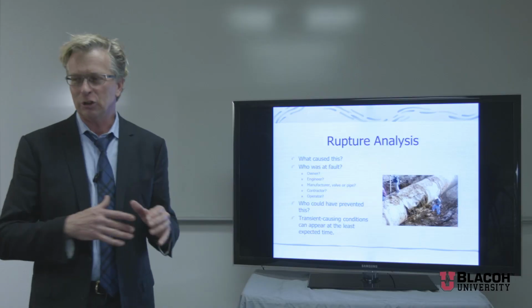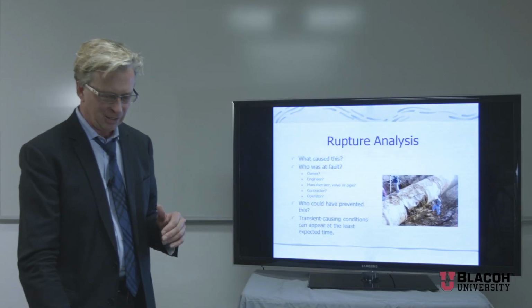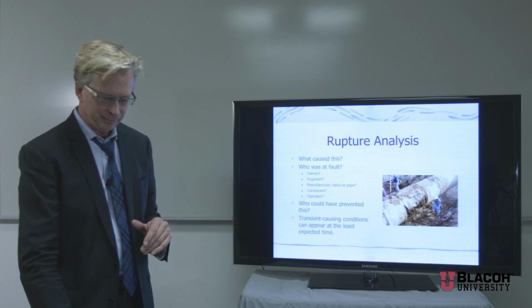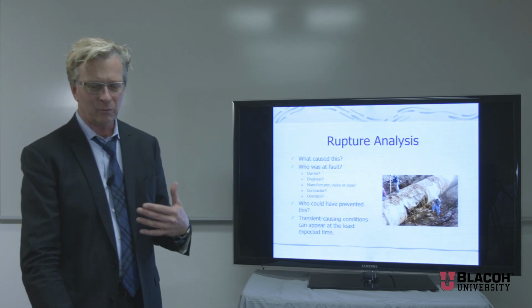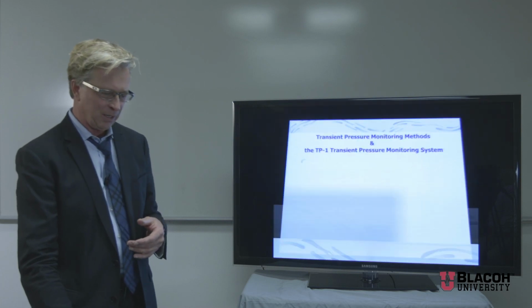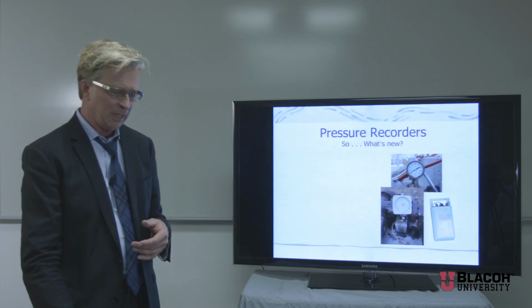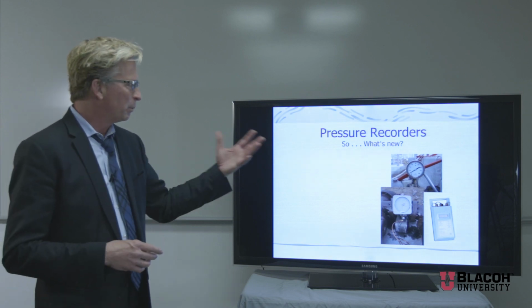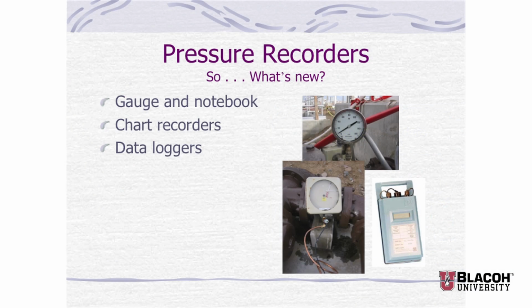What assumption are you making there? And a lot of manufacturers will say, oh, my pipe, we've tested it to a full vacuum, it stayed fine. All right, that was in their laboratory and they pulled a vacuum on it, but it wasn't a transient shock wave traveling through the piping system. So that's where there's a difference of opinion on the piping material and what is an acceptable negative pressure wave. So it's recording the data, and if we look at pressure gauges in the system, a nice liquid-filled gauge with a pressure snubber on it is going to buffer out that shock wave that's traveling through the piping system.